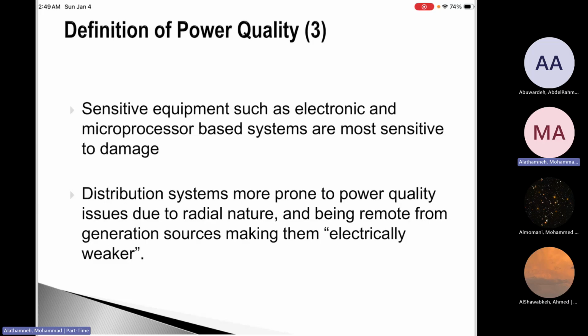Basically, radial feeders run longer distances from strong sources, with higher source impedance, more switching, and more faults. Engineers say the network is electrically weaker at the end of the feeders, meaning a disturbance causes a large voltage deviation. So when we have multiple feeders, like here, where this is the transformer and then there are multiple feeders, the customer at the end of the feeder sees the worst impact of the disturbance, the worst impact of power quality.